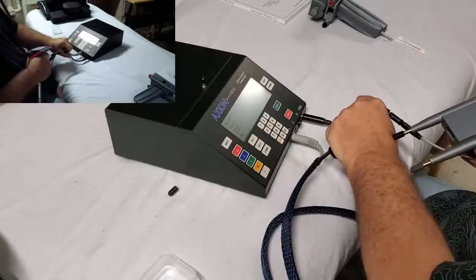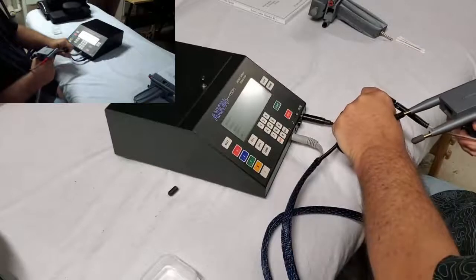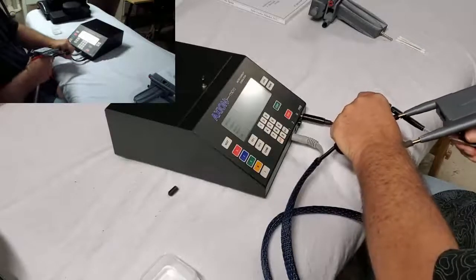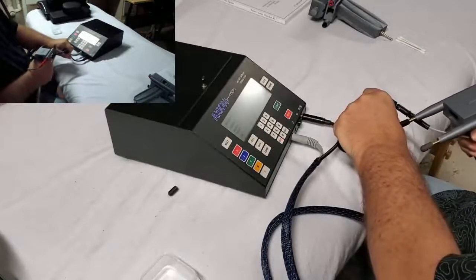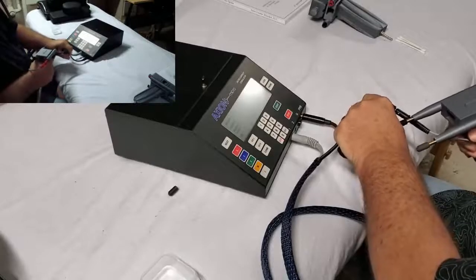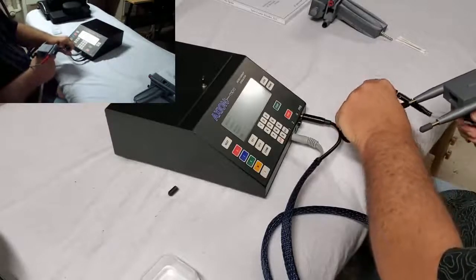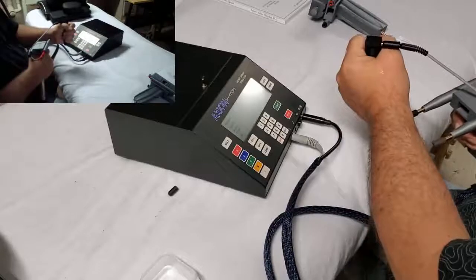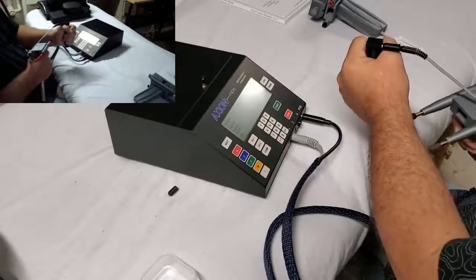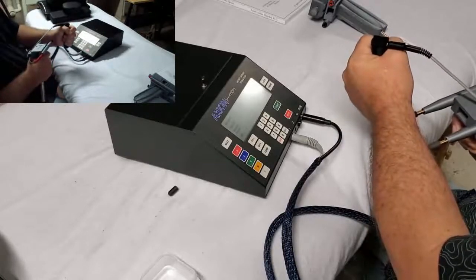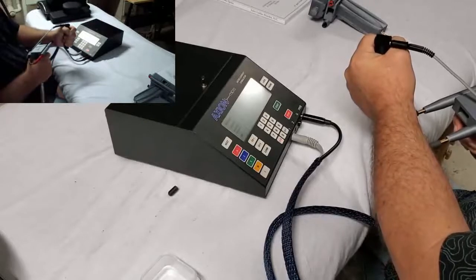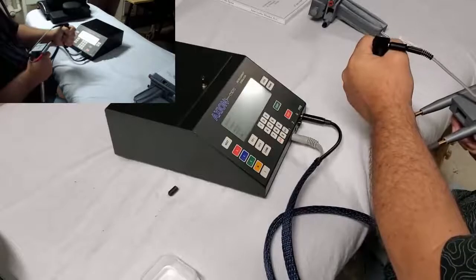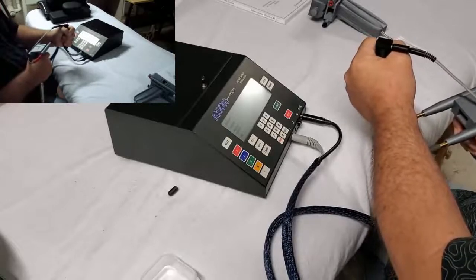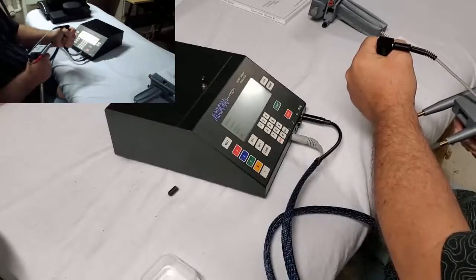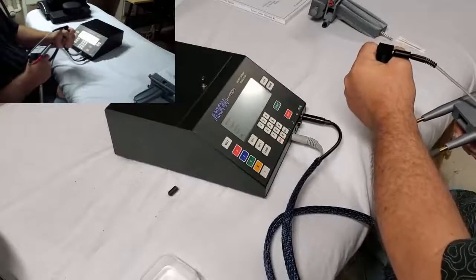You'll see that I can scan with just this one tip, and even if this other tip touches the skin, it doesn't make any measurements. So I can now use this probe on any area of the body to measure any acupoint and then treat that point by simply pressing the button. And I'm now delivering a treating current that is whatever is set on channel number 1. And then it returns to scanning.